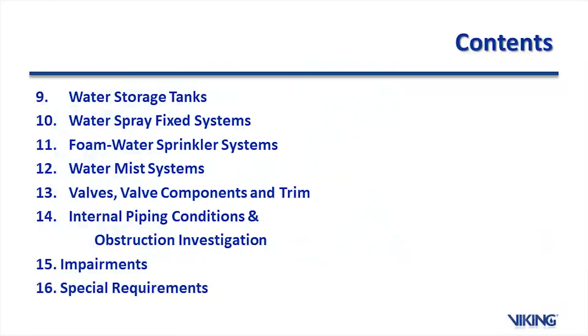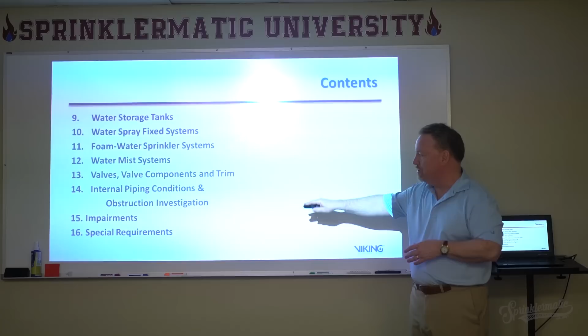The arrangement in NFPA 25 is basically: administrative chapters up front, then sprinkler systems, standpipe, private fire service mains, and fire pumps, all pulled out of the installation requirements, such as NFPA 20 for fire pumps. It goes further into water storage tanks, fixed water spray systems, foam water sprinkler systems, water mist systems, all the way through, with a couple of system maintenance issues at the end. The whole idea was to take all these ITM provisions and put them in one book, because even though various parts address different items, it's really one system, all of it together.